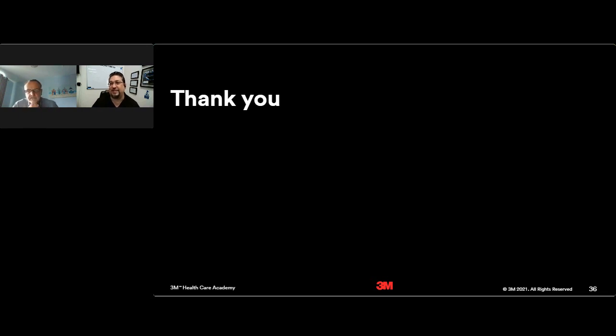Somebody says: I worked with plant engineers that refused to look at the steam quality because they say by definition steam is pure and it cannot be the source of staining. The site was seeing staining on instruments and tray liners. They were reluctant to read ST79 or TIR34 because it was not from the ASHRAE world. Do you have any recommendations on how to approach that type of situation?